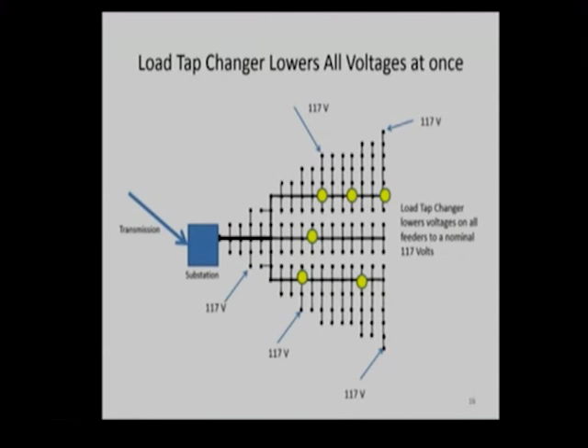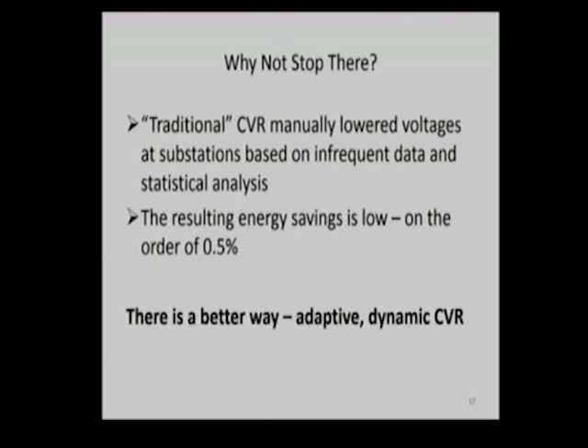Traditionally, conservation voltage reduction was used in states like California back in the 70s. When they were having peak energy problems, they actually required their utilities to do an older form of CVR. But what they really did was they took statistics and went out and measured voltages, and then they kind of tried to just lower the voltage at the substation without knowing what was really happening out on the grid. So they had to do it cautiously. It didn't provide much savings, and it was done manually. So they had to send people to the substations regularly to change the voltages, and eventually that was pretty much abandoned. But there is a better way, and that's what I'm going to talk about now, which is to do this adaptively and dynamically with computers and a communication network.